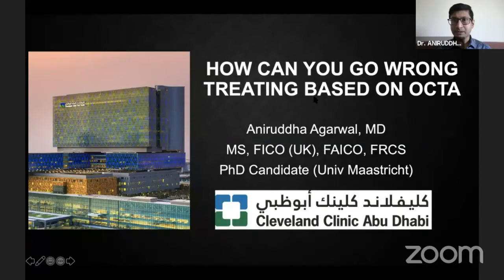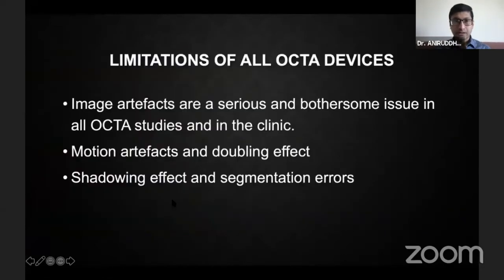I'm going to be speaking about how you can go wrong when you're treating on the basis of OCT angiography. At the outset, I'd like to state that there are a number of limitations of all the OCTA devices. The most important issues are image artifacts, which are a serious and bothersome issue present in all the OCTA studies and also in the clinics. We also face issues with motion artifacts and doubling effects, and we also have shadowing and segmentation errors.